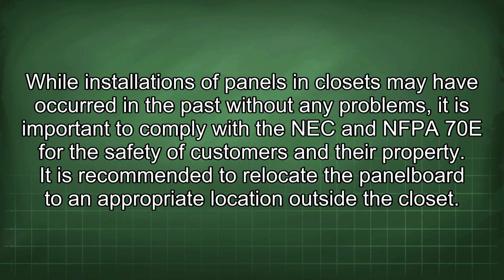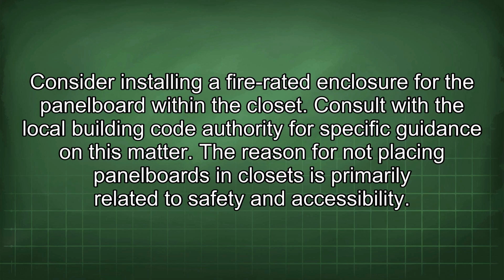It is recommended to relocate the panel board to an appropriate location outside the closet. Consider installing a fire-rated enclosure for the panel board within the closet. Consult with the local building code authority for specific guidance on this matter. The reason for not placing panel boards in closets is primarily related to safety and accessibility.